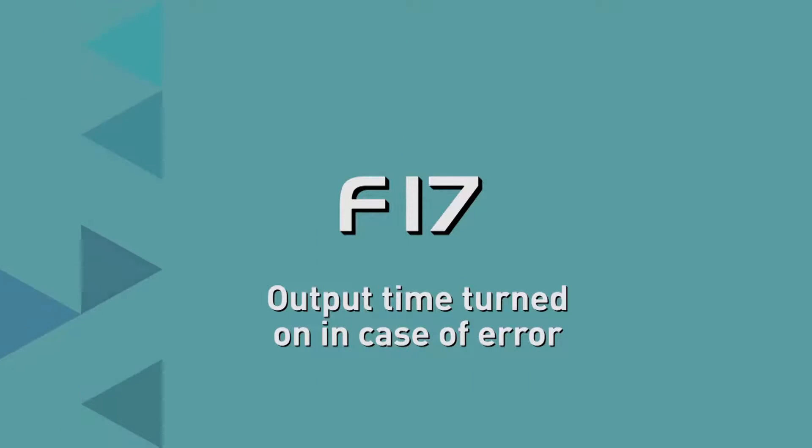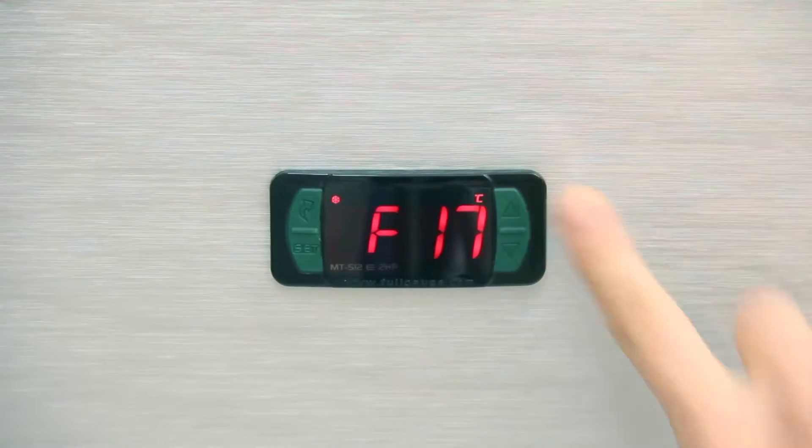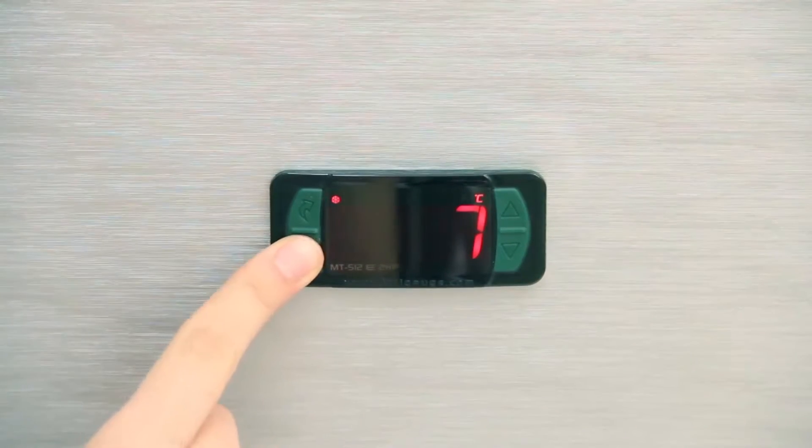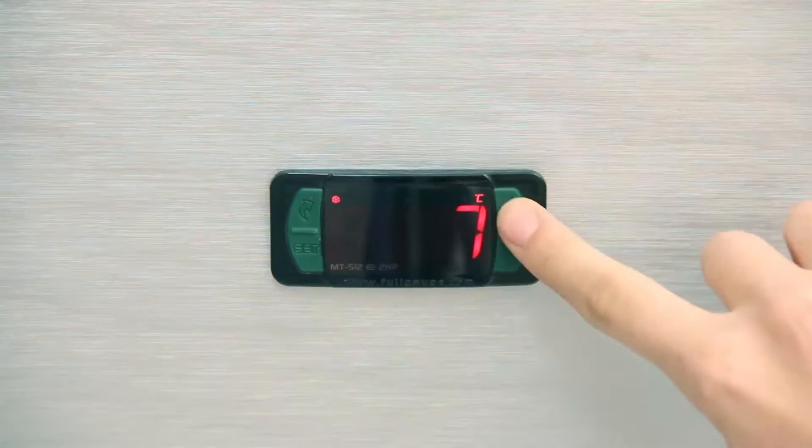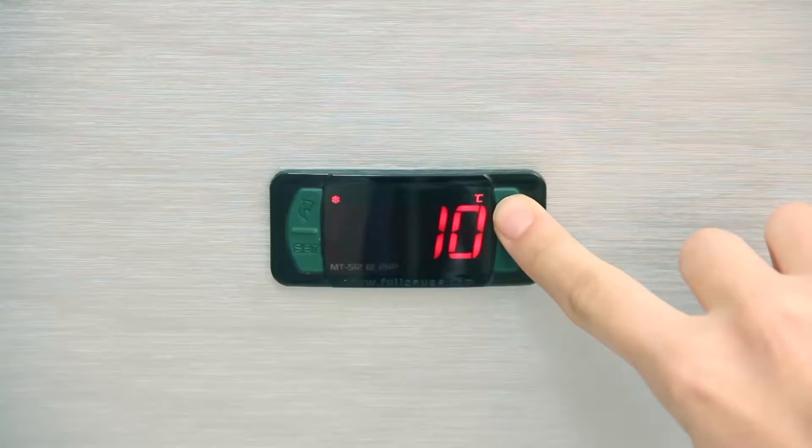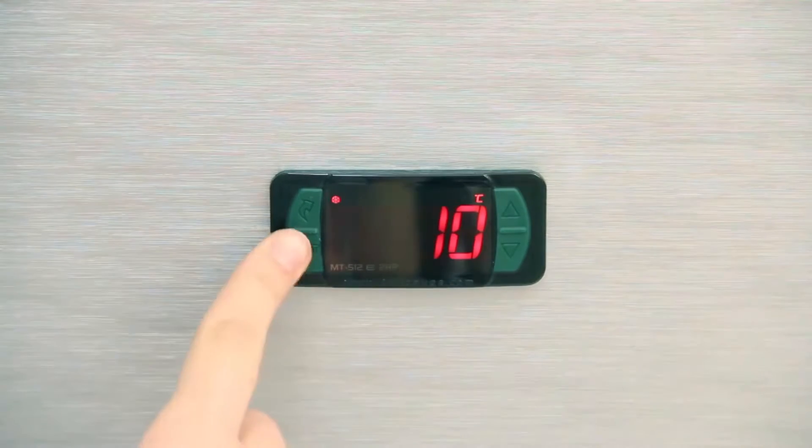F17, Output Time turned on in case of error. It sets the minimum time the compressor will stay on if the sensor is disconnected or out of the measurement range. In the example, we opted for an increase of 10 minutes.